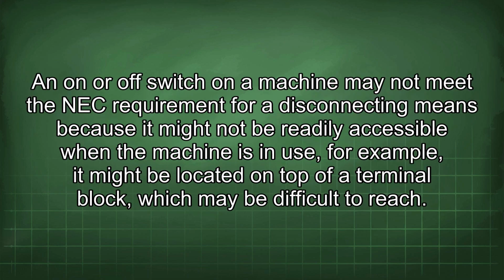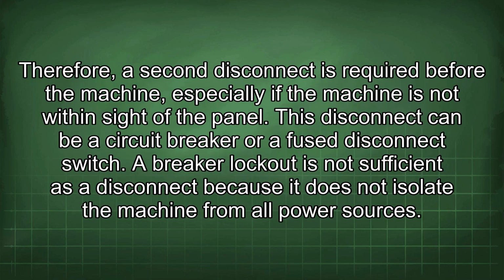An on or off switch on a machine may not meet the NEC requirement for disconnecting means because it might not be readily accessible when the machine is in use. For example, it might be located on top of a terminal block, which may be difficult to reach. Therefore, a second disconnect is required before the machine, especially if the machine is not within sight of the panel. This disconnect can be a circuit breaker or a fuse disconnect switch.